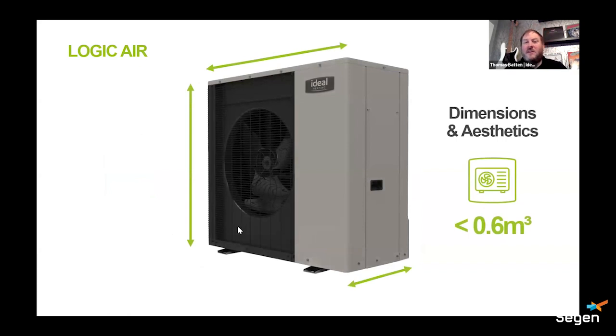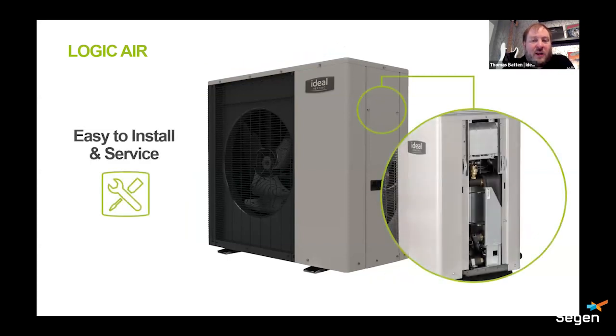Fairly compact in terms of dimensions as well, and also clearances are excellent on Logic Air. They're all under 0.6 meters cubed, so no issues with getting them passed off as permitted development. And you only need 100 mil clearance on the back and on the left-hand side of this heat pump. You only need to save yourself about 500 mil to get this panel off in order to be able to do the install and the wiring. And that panel is the only one that has to come off on this heat pump. So you take that off, you've got your air vent there and your wiring terminals at the top, and that's all you need access to.